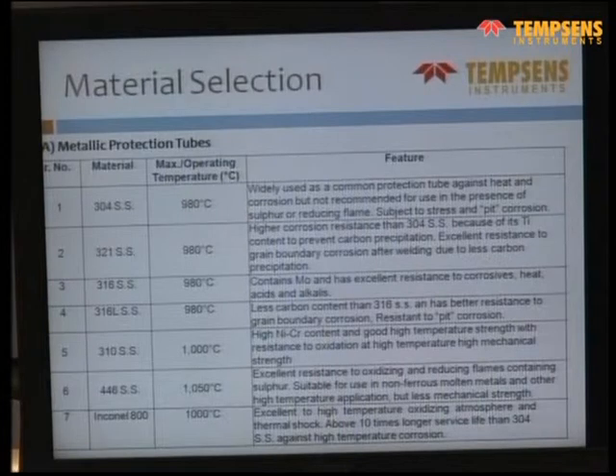Now coming to the various materials which are available for the thermowell. So we start with the metallic protection tubes or metallic thermowells or bars, which can be drilled and made into forms of thermowells. So we have a selection from SS 304, 321, 316, 316L, 310, 446, Inconel 800. So one consideration is obviously temperature. There's a different temperature range for each of these elements. And then according to the type, there's also particular usage.